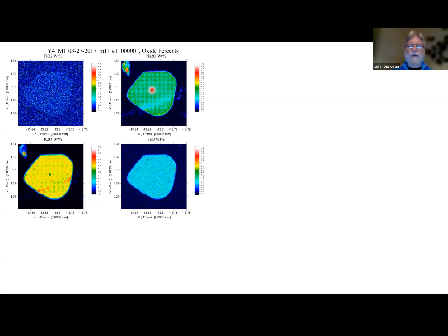But it doesn't matter if it's irregular, we can correct for it. So here's the correction without TDI. Okay, and how do we do TDI on maps? We do multiple frames. Instead of doing one long map, we acquire a number of short maps, okay? And the software is designed to automatically take each pixel and extrapolate it back to 0 time. So we get a perfect correction for every pixel in the map, for not only the matrix and background and everything else, but also for the TDI effects, which stands for time-dependent intensity, if I didn't explain that.